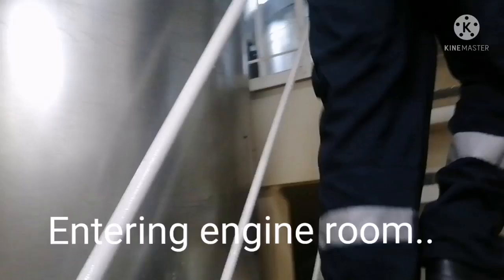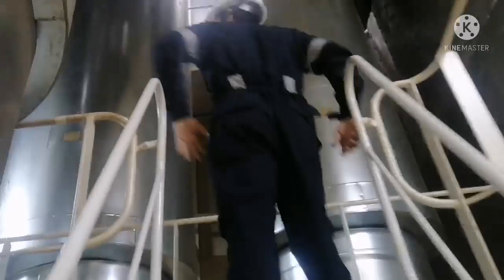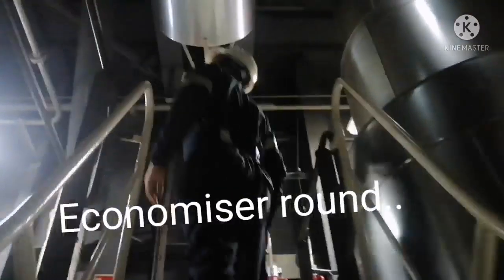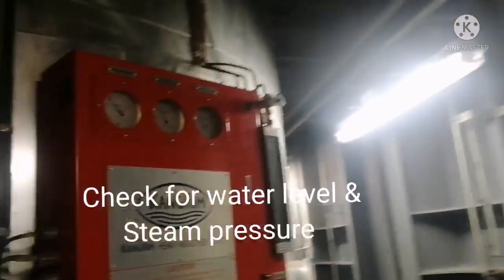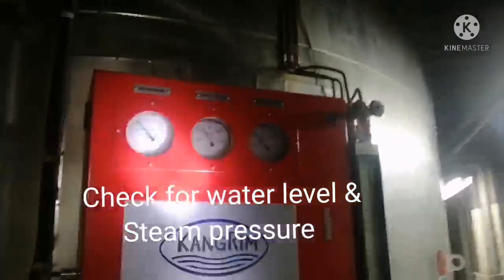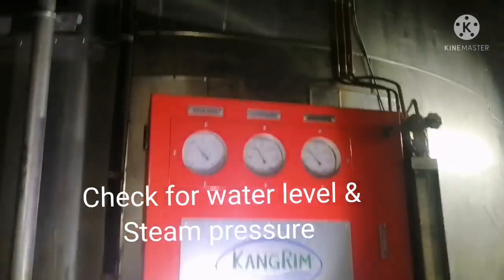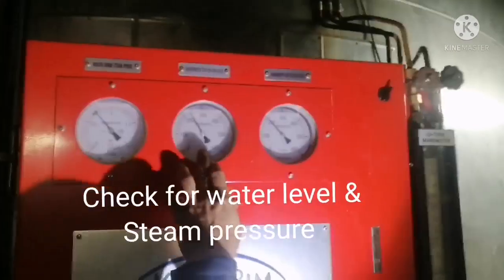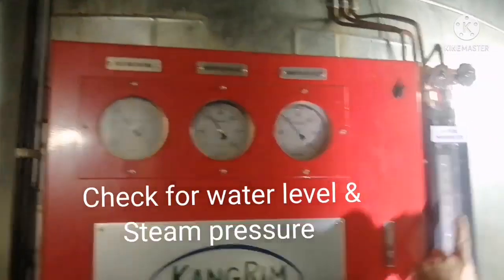Now I am entering the engine room. So, engine room economizer platform, I am in. All you have to do is check the economizer visually from outside, and check the water level and steam pressure in the economizer. You can verify with the gauge, and you can see the water level in the water level gauge glass.